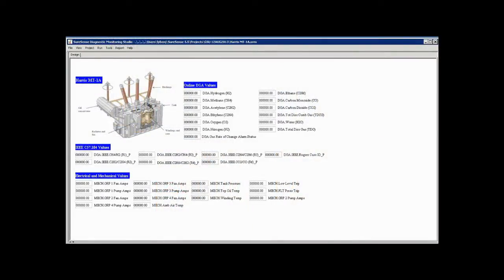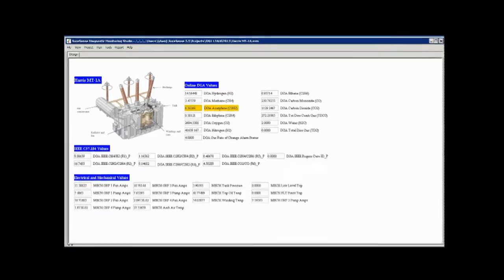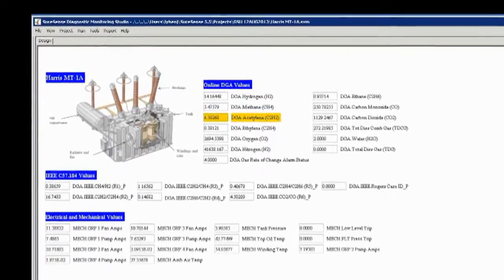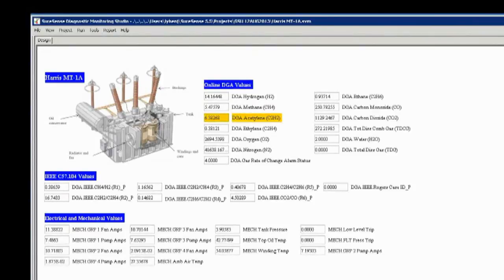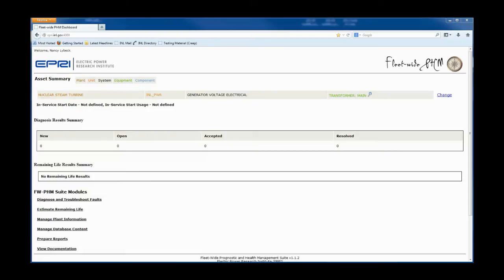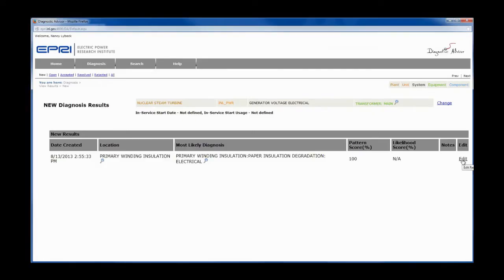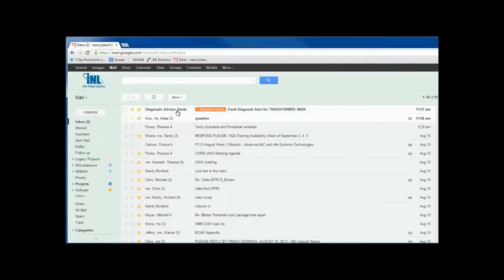SureSense pattern recognition software monitors the data and creates alerts when relative concentrations of acetylene, carbon monoxide, and carbon dioxide to carbon monoxide ratio exceed recommended levels. An early indication of high acetylene concentration in the transformer's insulating oil is detected and logged. The pattern recognition software provides immediate detection of the problem based on IEEE recommendations. The Diagnostic Advisor is scheduled to check its online data sources periodically to discover new warning events. When a new event is detected, the Diagnostic Advisor runs analysis and creates a new diagnostic result and simultaneously notifies responsible personnel with an email.